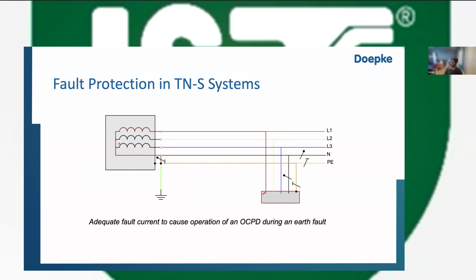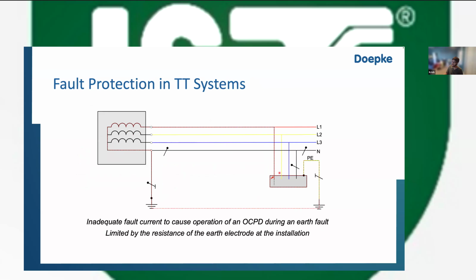Fault protection in a TN system, as I explained, you have a lot of current that will flow through, enough to cause adequate fault current to cause operation of an OCPD during an earth fault. But in a TT system, let's say this has a resistance of 100 ohms, for example. So 230 volts divided by 100 ohms, we're talking only 2.3 amps of current. There is inadequate fault current to cause operation of an OCPD during an earth fault. They are limited by the resistance of the earth electrode in the installation. So essentially what happens is that you don't have enough fault current.